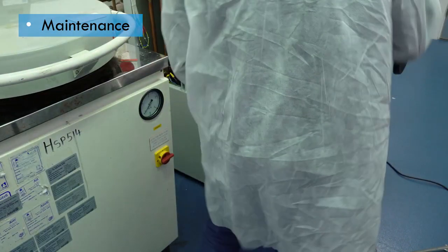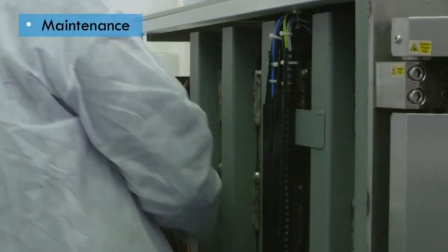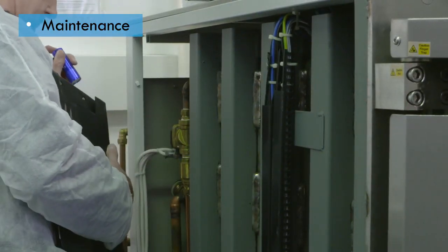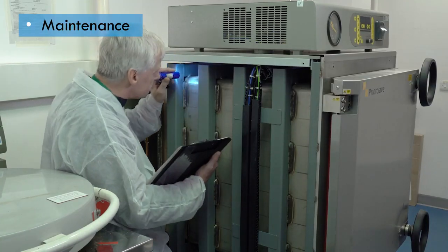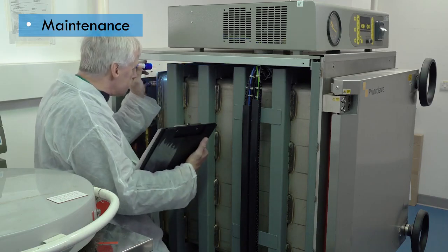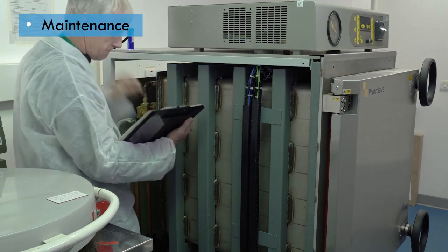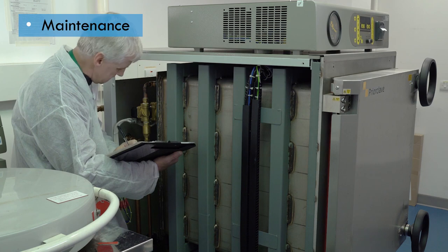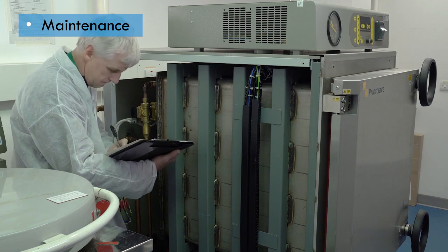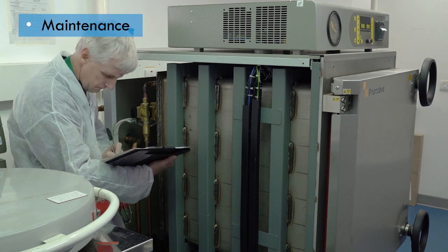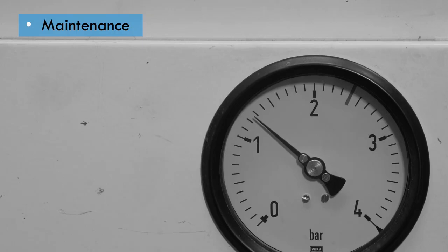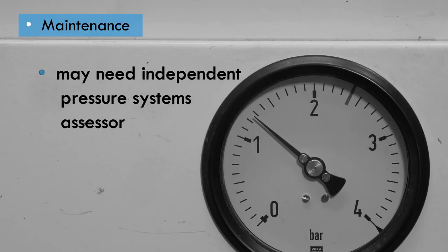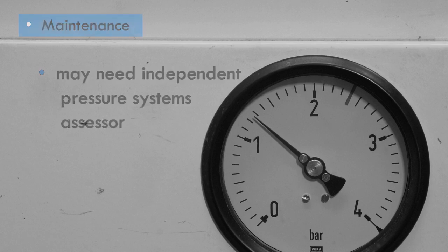Autoclaves should be serviced at least annually and tested by a specialist contractor who can make sure the set temperature and pressure cycles are accurate and check the overall condition of the autoclave. This is important because of the high pressures at which they operate. Because of these high pressures, in some countries it is also a statutory requirement for autoclaves to be tested by an independent pressure systems assessor.